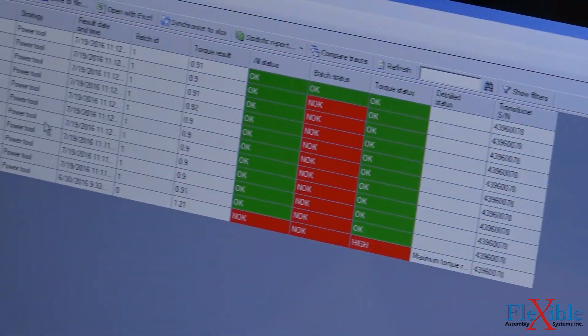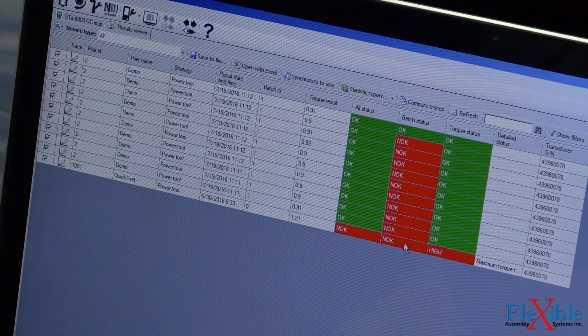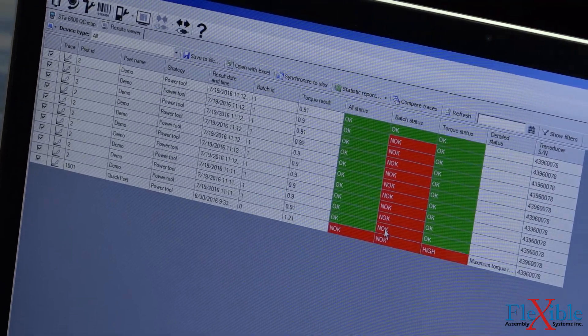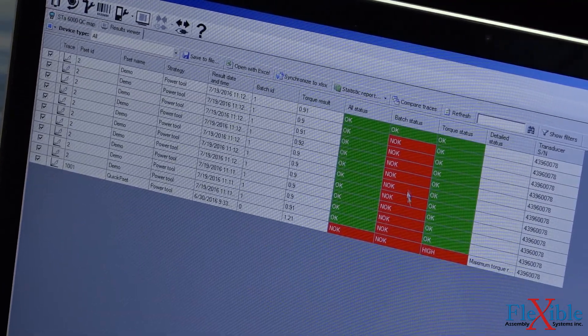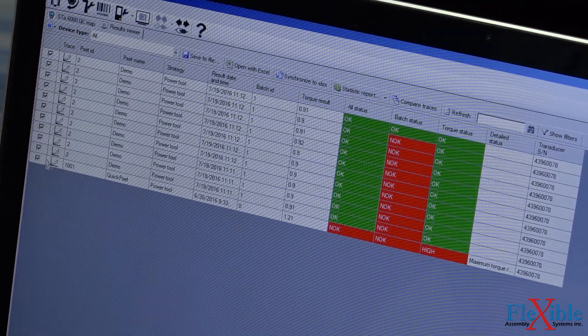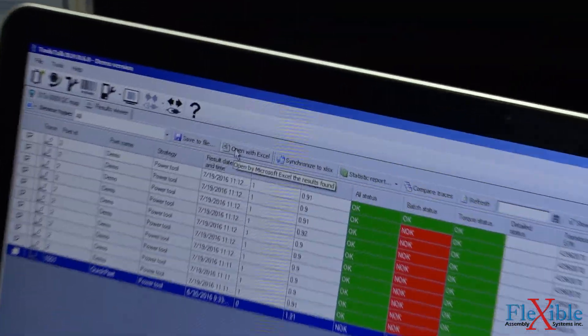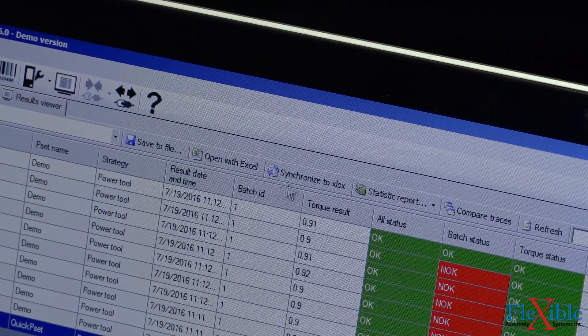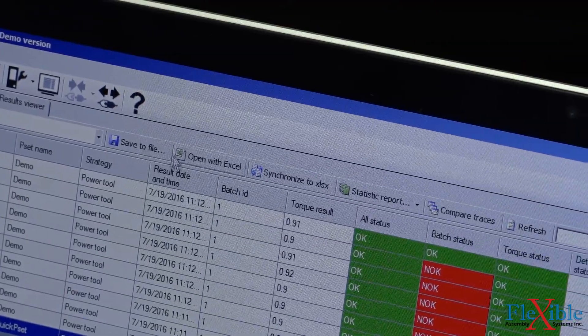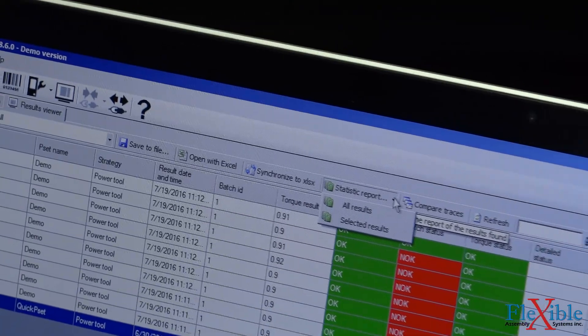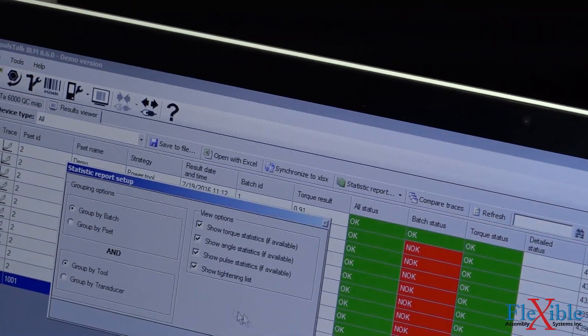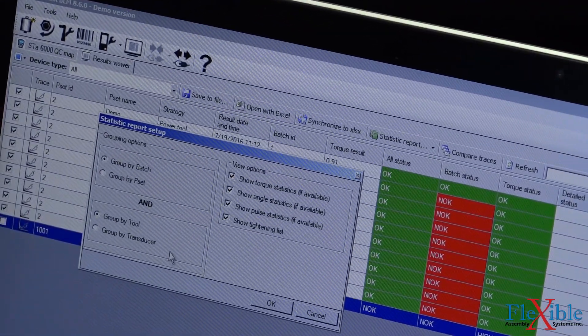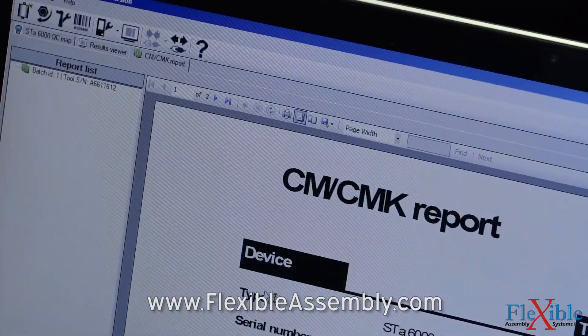The batch status will display not OK until the tenth rundown when the batch is complete. We removed our first result, which was a test by unchecking it. Again, here we have many options for saving. We create a new statistic report with only the ten selected rundowns, and again we could save and print this condensed version without all the graphs from the previous versions.